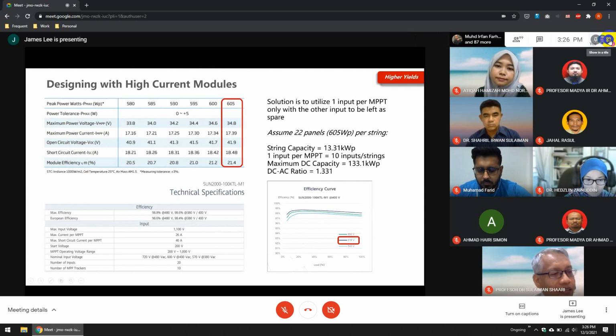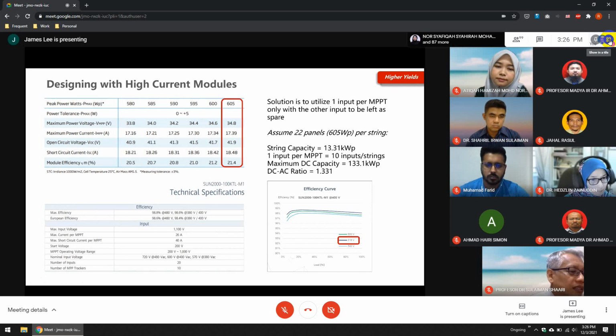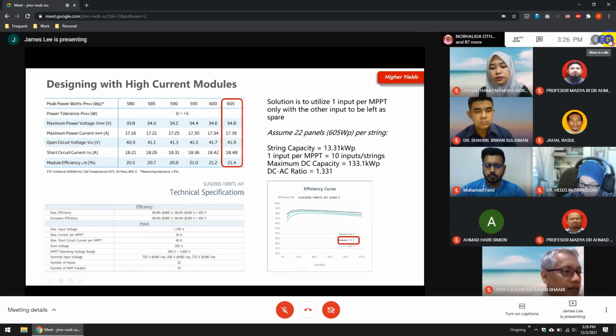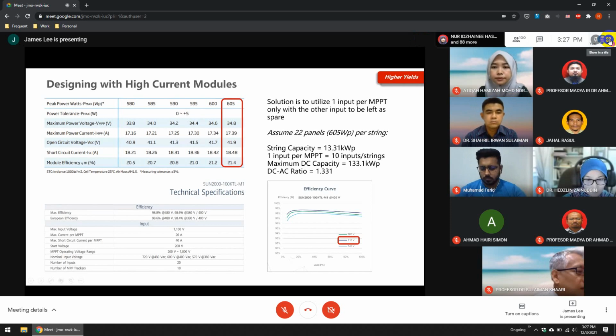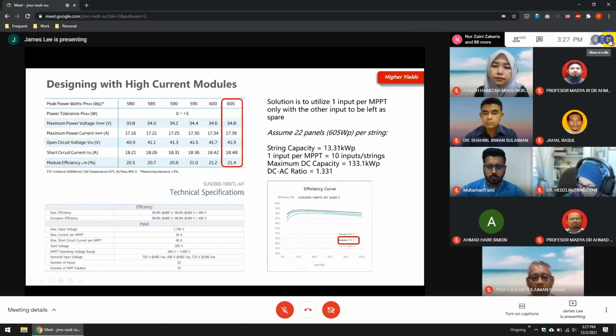The other part I like to highlight: the VMP is 34.8. If you multiply that by 22, it's about 700 odd volts VMP. When you also include the temperature coefficient, using a general rule of thumb of maybe 10%, the inverter is able to operate at its highest efficiency, which is in the range of about 620 volts. So when you bring it back down, you are well within the range of the higher efficiency.